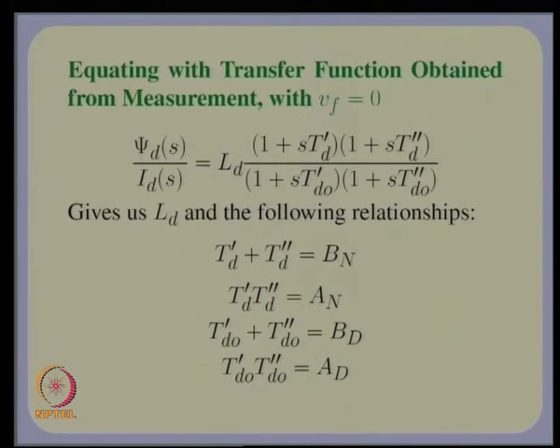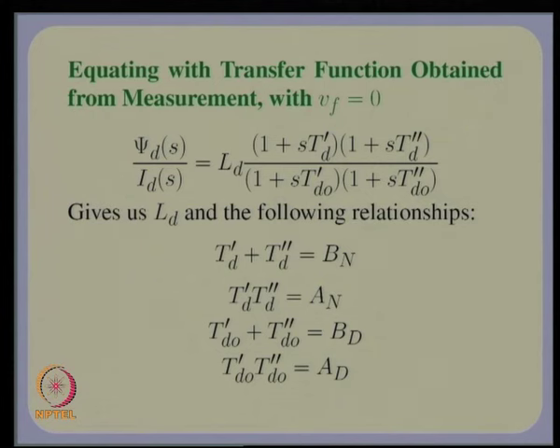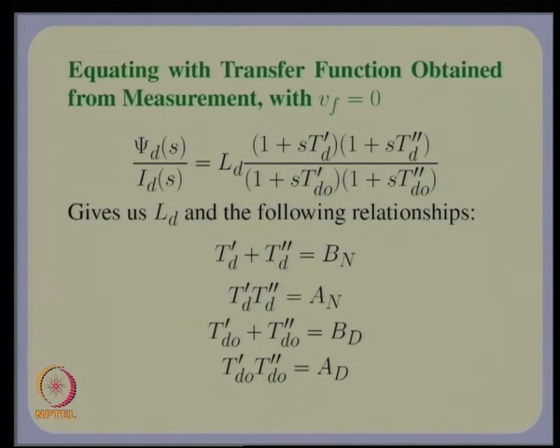If we carry out a measurement with v_f = 0, what we effectively get are the coefficients of the transfer function, or equivalently the time constants T_d', T_d'', T_d0', T_d0'', and L_d. The coefficients a_n, b_n, b_d, and a_d are related to these time constants by four equations. These are the standard parameters obtained from one measurement.